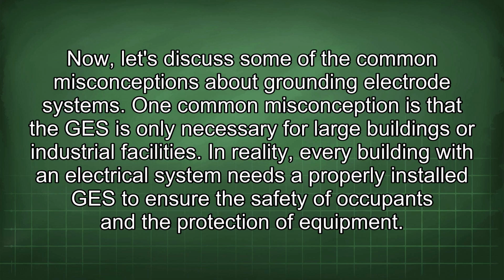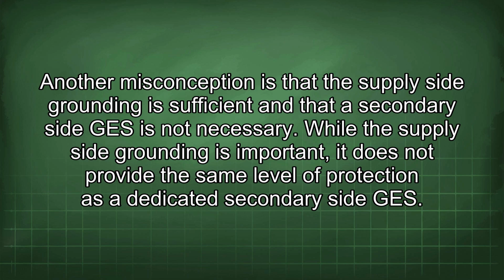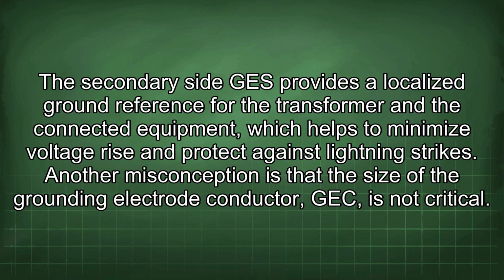Now let's discuss some of the common misconceptions about grounding electrode systems. One common misconception is that the GES is only necessary for large buildings or industrial facilities. In reality, every building with an electrical system needs a properly installed GES to ensure the safety of occupants and the protection of equipment. Another misconception is that the supply-side grounding is sufficient and that a secondary-side GES is not necessary. While the supply-side grounding is important, it does not provide the same level of protection as a dedicated secondary-side GES. The secondary-side GES provides a localized ground reference for the transformer and the connected equipment, which helps to minimize voltage rise and protect against lightning strikes.